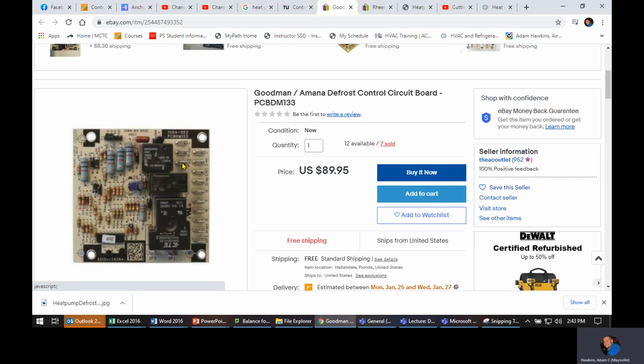And then you've got a PS2 and an RPS1. So what this is doing, RPS1 is sending red, 24 volts, out to a pressure switch, and then it's checking that switch, and assuming the switch is closed, 24 volts comes back on PS2. And then here's a common up here, another common.